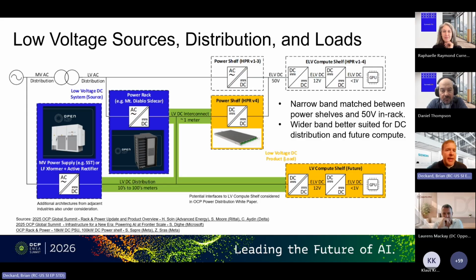But long term, where is the bottleneck? Right now we're talking about incredibly high currents as we scale data centers from triple digit kilowatts into the megawatt territory. With this, we have a need to consider the very practical, real thermal limitations of the 50-volt bus bar. This helps set the stage for a transition to higher, say 800 volts, power within the IT rack, no longer necessarily that 50-volt stage.